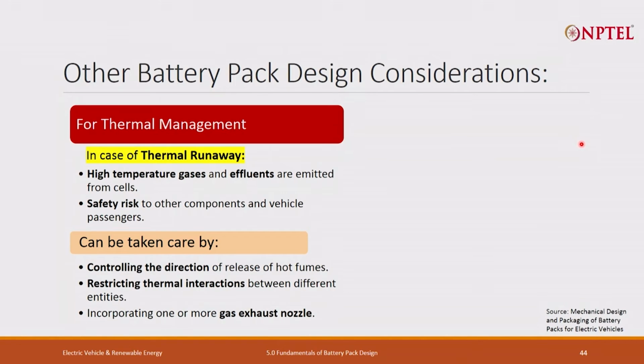So what care has to be taken? Care has to be taken by controlling the direction of release of hot gases or hot fumes, and by restricting the thermal interaction between two cells or between two components. You can have one pressure relief valve or multiple pressure relief valves, depending upon the size, capacity and requirement of that particular pack.